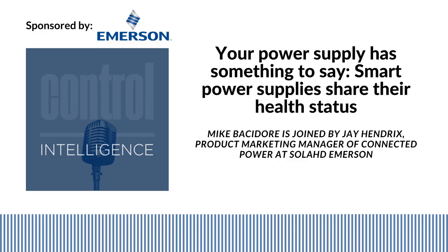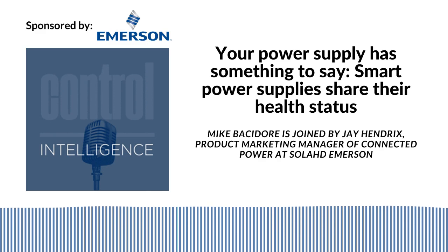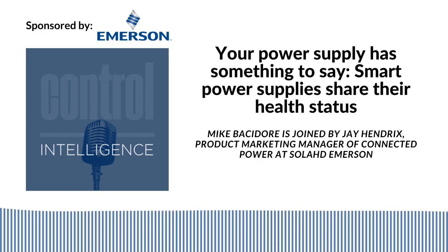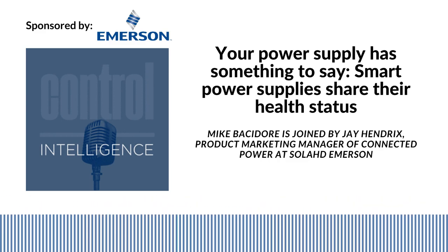So what we want to do is enable the operators and service technicians to catch a problem way in advance. For example, something that might be useful is to look for unbalanced loads. In batch production, they use redundant power supplies because it's really important that they keep it running. But they might want to look at unbalanced loads, or whether additional loads have been added to the power supplies over time, because things happen in a plant and things are added. They never know when that may happen, and after the fact is too late. So a connected power supply can provide you real-time information, such as the input and output voltage and currents, power supply temperature, power supply alarms and events, and even useful life information.